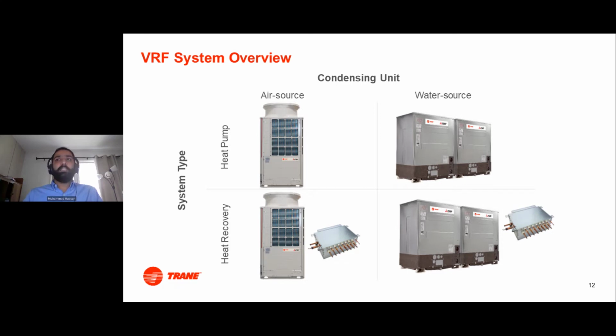So, broadly speaking, there are two types of VRF systems. There's heat pump and there's heat recovery. Heat pump is typically straight heating or cooling. That is, all of the indoor units are in the same thermal mode. Heat recovery has an additional component called the branch box. The branch box has heat exchangers, solenoids, and controls that are built into it to allow simultaneous heating and cooling. That's become a hallmark of VRF systems.